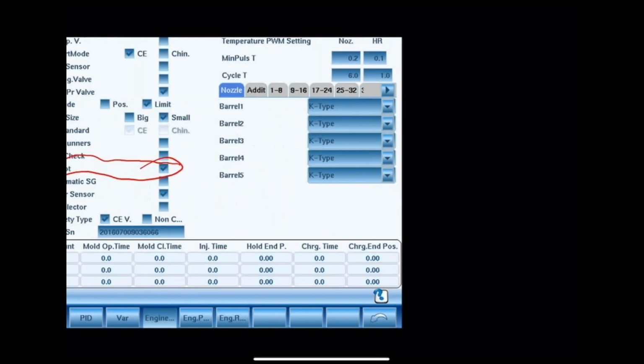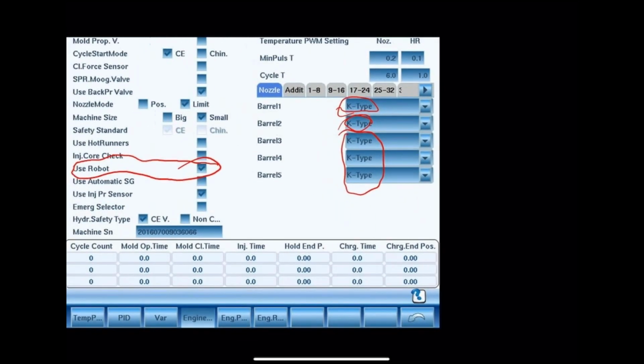And if you're using different types of thermocouples, you can change them right in these boxes. If you change one, change them all to the same type. You never want to mix thermocouple types. So you can actually have J or whatever thermocouples you want to use. Actually, K is the most accurate and the best, highest temperature zone. So that's usually the best thermocouple to use anyways.